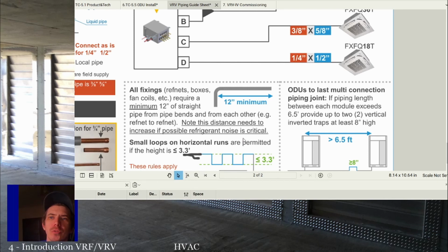Note this distance needs to increase if possible. Refrigerant noise is critical. So if you don't have at least 12 inches of straight pipe, think about it like this. You're going to have a lot of turbulence as that refrigerant splits and then splits again and then splits again. You're trying to minimize that. You're trying to get some straight flow before you make another change of direction or something like that. So you need at least 12 inches of pipe there. But because of that turbulence, even if you have at least 12 inches, it's still going to be noisy. We don't think about refrigerant as noisy, but refrigerant can be pretty noisy, right? Refrigerant lines running, especially at high velocity, you can hear the refrigerant flowing through those pipes. Think about listening to it right next to a TXV or something like that.